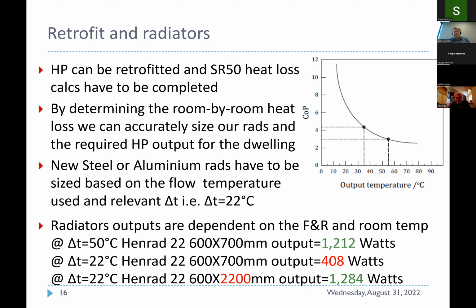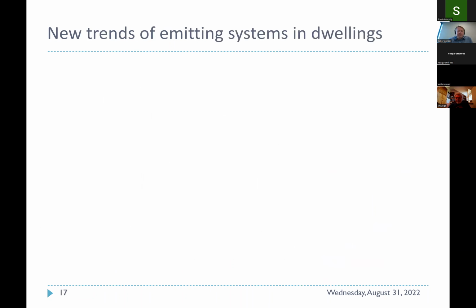So it's very important at an early stage to make all these calculations and to see if you actually have the space to fit one radiator, or you may have to fit 2 radiators, depending on the type of retrofit. Sometimes in a kitchen dining small semi-D scenario, you may not be able to do that. You'll have to look at using vertical radiators and other solutions, fan coils that will give better outputs and so on. Talking about fan coils, this brings me towards the end of it.